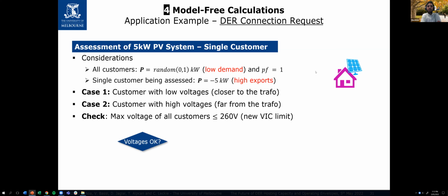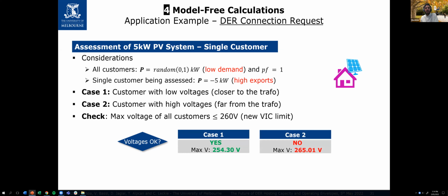So we do the check to see if voltages are okay. For case one, yes, this customer can host a 5 kilowatt PV system without creating voltage issues in the low voltage network, because the maximum voltage we find is up to 254 volts. For case two, no, this customer cannot host a 5 kilowatt PV system because the maximum voltage of some customers goes way beyond the statutory limit.